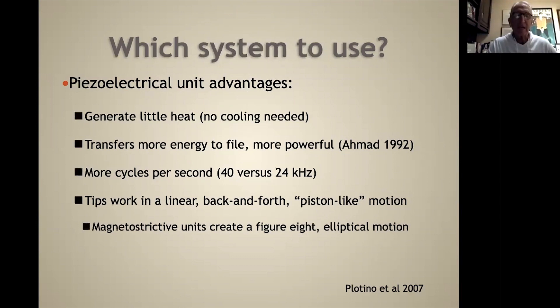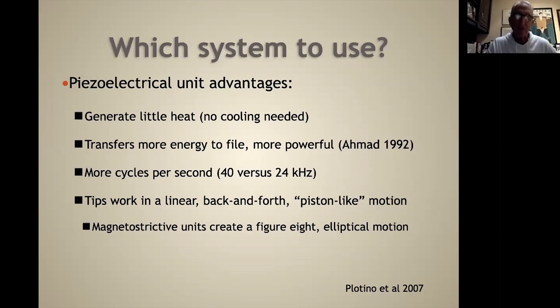So which system do we use? The piezoelectric unit has many advantages: it generates little heat with minimal cooling needed, and it transfers more energy to the file — more powerful — as shown by Ahmad in 1992. It works at 40 kHz versus 24 kHz for the magnetostrictive principle. The tips work in a linear back-and-forth piston-like motion, as versus the magnetostrictive units, which create a figure-eight elliptical motion used in the Cavitron. We can't use figure-eight because that would destroy tooth structure, so we work with the piezoelectric principle.